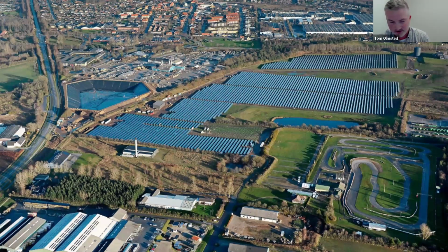Separate example, really quick. I thought it was just a good picture of a solar thermal generating system, and that hexagonal hole in the ground is actually pit thermal energy storage. So heat is generated typically at night. Denmark has a lot of offshore wind. They have negative energy prices at night when there's excess wind energy. So they optimize heat pump operations to start generating heat when electricity is free or you're paid to do it, and they just pump hot water into pits or tanks, borehole fields, or aquifers to store.